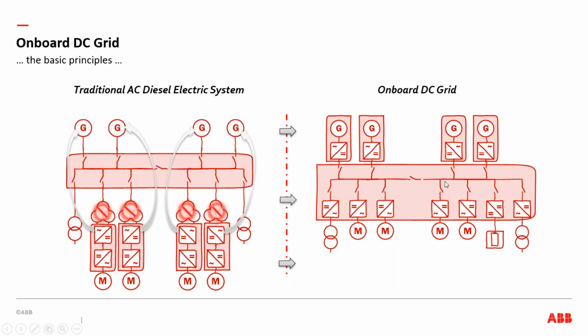One of the challenges with DC power distribution is that breaking the current is much more difficult. So for fault tolerance, the bus tie associated with a DC system has traditionally been much larger and heavier. One enabling technology that's allowed us and a few competitors to start marketing these systems is that we've solved that bus tie problem with a cost-effective, smaller, simpler solution. That's a key enabling technology.